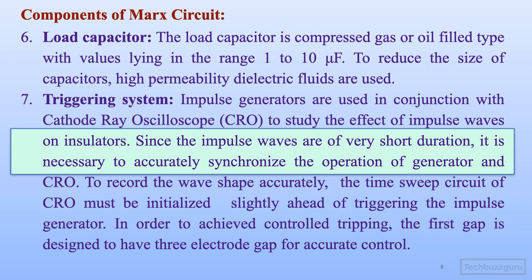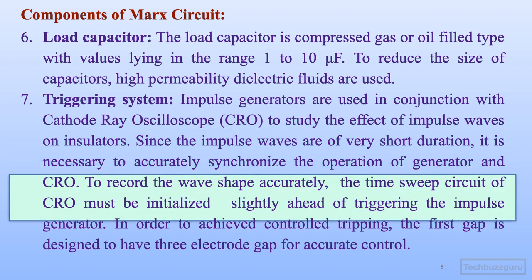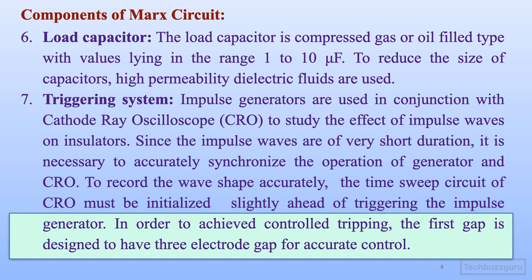Impulse waves are of very short duration, and to accurately study them, synchronization of the CRO with the impulse generator must be achieved using a time sweep circuit. The time sweep circuit of the CRO is initialized slightly ahead of the moment when the impulse generator is triggered, to record the wave shape accurately. To achieve controlled tripping, the first spark gap is usually designed to have three electrodes, also called a trigatron type of arrangement.